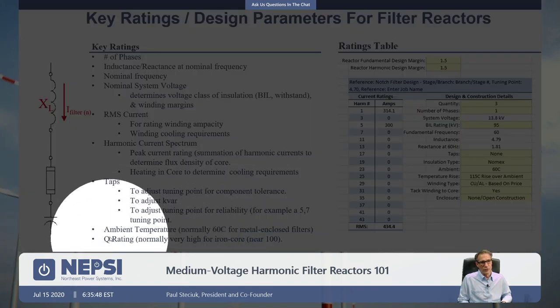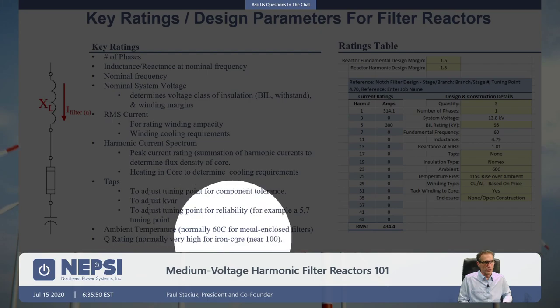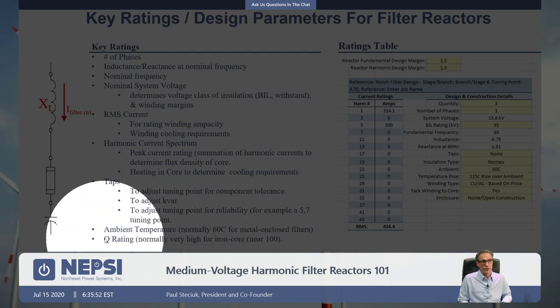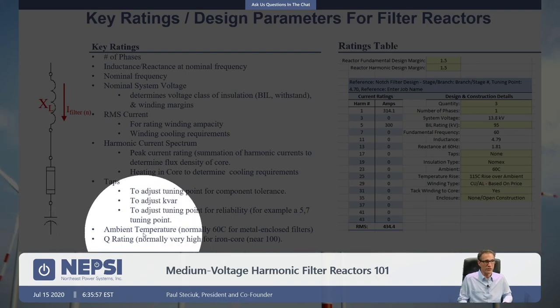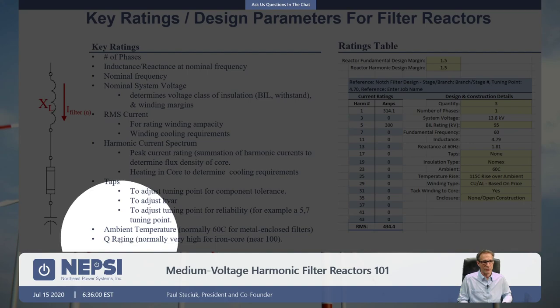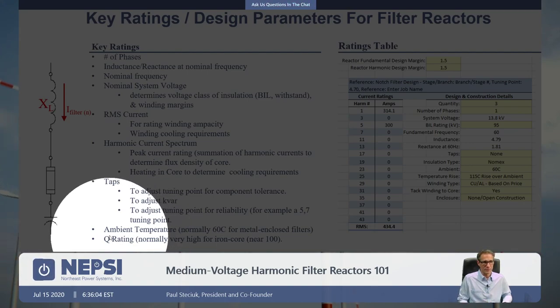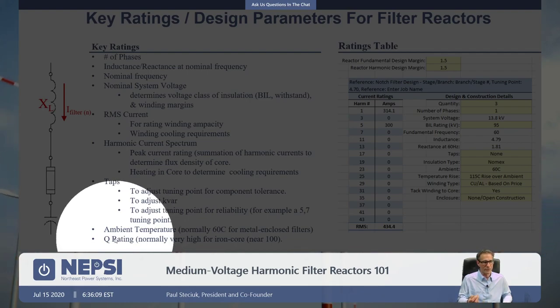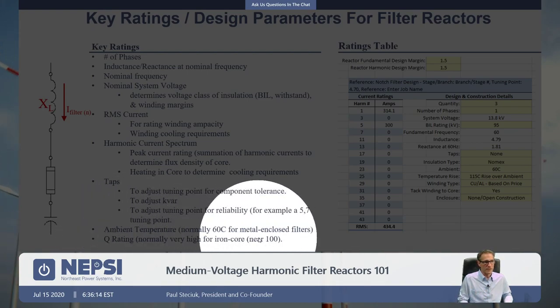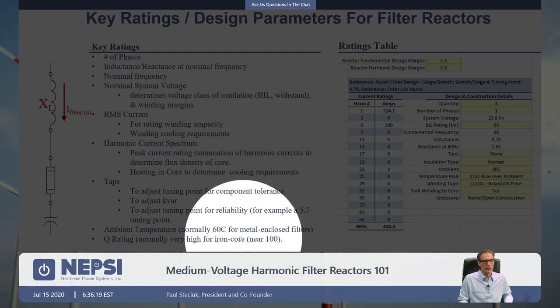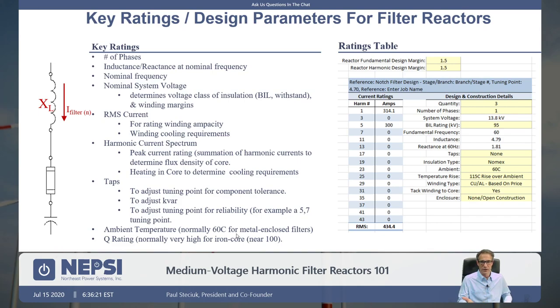The Q rating — for iron core reactors, you don't have a lot of flexibility in the Q rating, which is just the X-over-R ratio of the reactor. It's often specified at the tuning frequency. For iron core reactors, you're stuck with whatever Q comes out from the design based on resistance at rated temperature. We're seeing values typically around 100 for iron core. For air core reactors, values are around 60. The air core guys do have a way of modifying the Q factor.